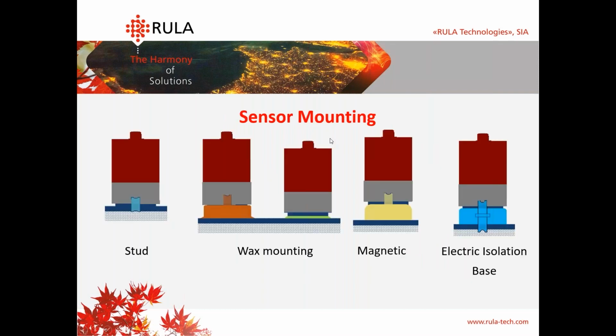And now let's talk a little bit about sensor mounting. It's really important during the test. If you fix your sensors badly, you'll get errors and emergency stops during the test, and there are 5 main ways of sensor mounting. The most basic one is mounting with a stud. You place a stud in the shaker table and screw a sensor on it. Also, you can use wax to mount your sensor. You can place a magnet on the bottom of your sensor and place it on the metal. And in some kind of calibration labs, it is usually used with an electric isolation base.